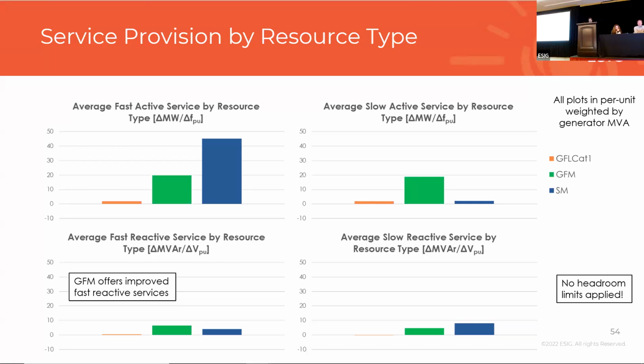Then there's slow reactive service, due to the AVRs and the voltage control capability that's there. It's comparable, not too much difference between the synchronous machine and the grid forming plant. We don't have GFL category 3 here, but you'd see that it would fall between the orange curve and the green curve in this evaluation, showcasing the evolution of the spectrum of services.